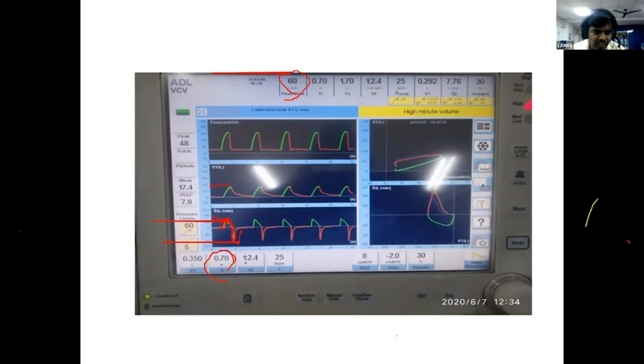And what is the I:E ratio? This is one of the important things for a patient who is having COPD. Yes, the I:E ratio, inspiratory to expiratory time, should be 1:2. If you are increasing the expiratory time to 4, what is the meaning of that? When the patient is having more CO2 retention and you increase the exhale time, that will decrease the CO2 level when the patient takes inspiration and expiration. Yes, that will come in ABG. We don't want to discuss that here, but you have to know the normal value of the I:E ratio. The I:E ratio is 1:2 or 1:2.5.